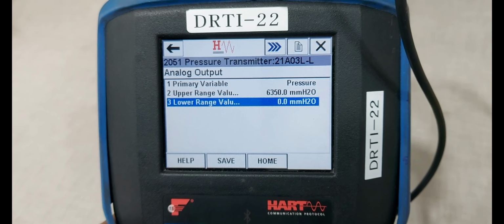Pressure calibrated tube connected to one T joint. One tube is connected to the low side, another tube connected to the high side. Next, power on the calibrator. Close the valve. Valve is closed. Next, we are applying static pressure to both sensors, high side and low side.